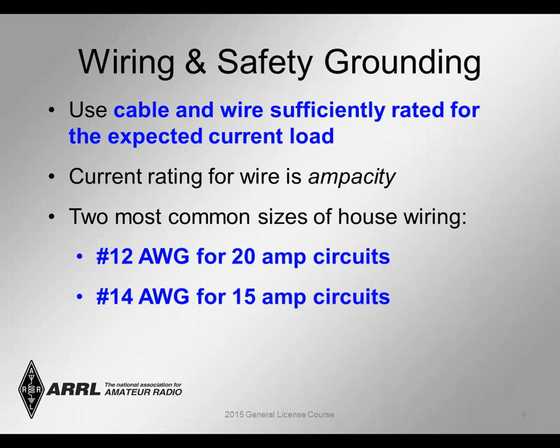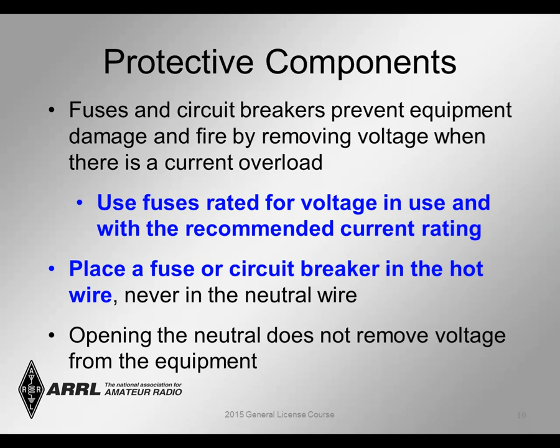Primarily, most homes are protected with circuit breakers. There's still places for fuses. Fuses need to be used for the voltage that they're rated with the recommended current rating. And you always want to put the fuse or circuit breaker in the hot side of the wire, never in the neutral wire. Opening the neutral doesn't remove the voltage from the equipment. If you look at a wiring diagram of a 120 volt, 220 volt house system, you see where that makes sense, that just opening the neutral, you'll still have the 120 volts applied to whatever device is connected to the circuit breaker.